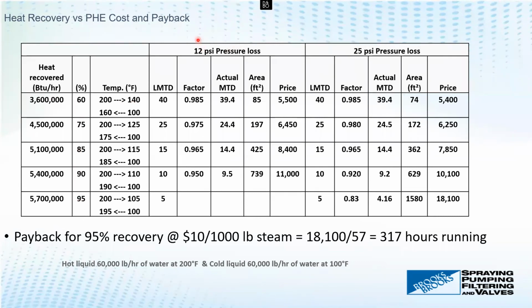One is a 12 psi pressure drop, and another is 25 psi, because these pressure drops are sort of a price paid for the heat exchangers. We prefer slightly higher pressure drop, but we need a comparison to see what the cost of a heat exchanger is for a given allowed pressure drop. The first one has a 40 LMTD with 60%. Actual MTD is 39.4 because it's a multi-pass unit, and there is some sort of co-currency in between plates. So area required was 85, and the price is 5,500 at 12 psi, and at 25 psi, slightly less, but not that much.